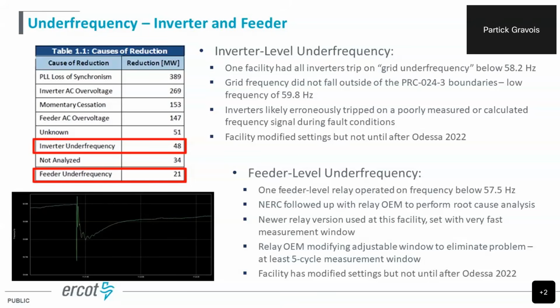So you really need to measure frequency over at least a 5-cycle window. But a lot of the way the requirements are written, they say, hey, if frequency goes below 57.5, you can trip immediately. And that's what they're doing. They're setting no time delay. So some of these devices, both inverters and breakers, are having this reading of below 57.5 hertz and tripping automatically. So we're really trying to eliminate this completely from the system. And this is something the industry needs to address. NERC has changed some of their standards, and they're going to continue to modify the standards to really get this point across to not be tripping due to frequency during these fault conditions. So both of these facilities had issues again in 2022. So we'll come back to this as well.